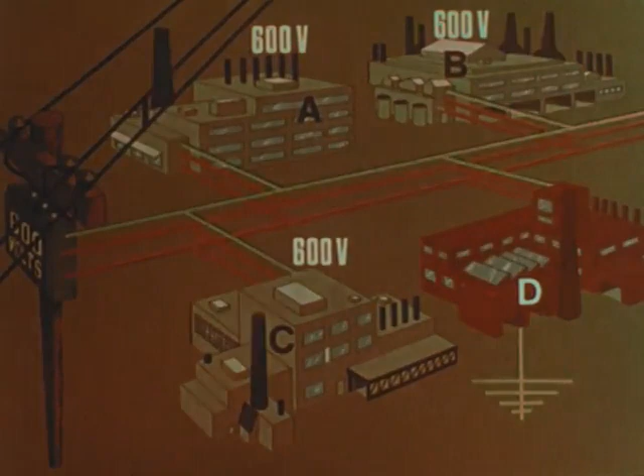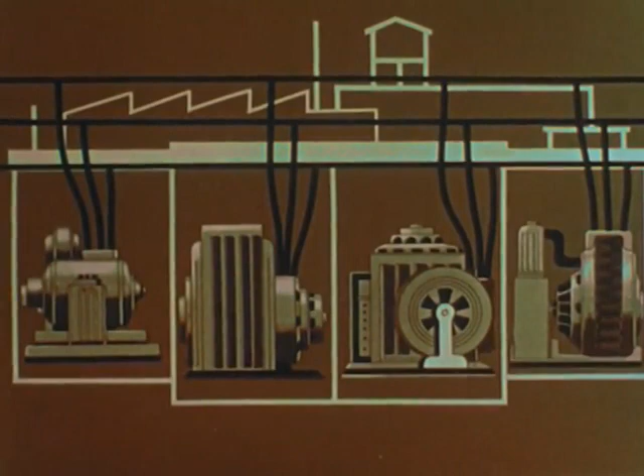A similar situation can develop in a single building where the service from a three-phase transformer is used to supply a number of different departments. A ground fault in one piece of equipment will again produce zero potential to ground in the affected phase and cause a rise to 600 volts on the other two phases throughout the entire building.